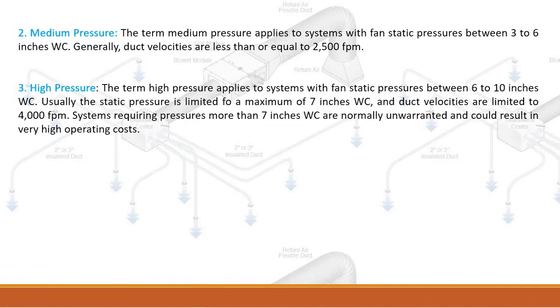Medium pressure applies to systems with fan static pressures between three to six inches WC, with duct velocities less than or equal to 2500 FPM. High pressure applies to systems with fan static pressures between six to ten inches WC. Usually the static pressure is limited to a maximum of seven inches WC, and duct velocities are limited to 4000 FPM. Systems requiring pressures more than seven inches WC are normally unwarranted and could result in very high operating costs.